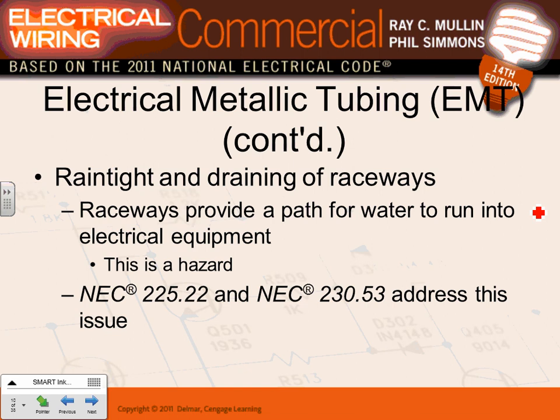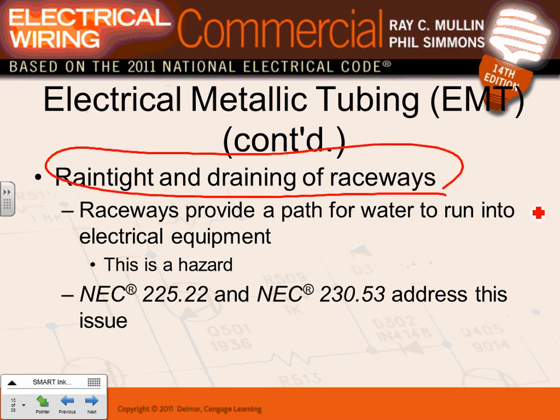Drainage of raceways: as you bring raceways inside the building, you don't want to channel water from outside to inside and dump it right above your switchgear. You have to provide a path for water to drain away from electrical equipment. As you bring conduit in, you need an elbow so that water can drain away. Inspectors and project managers will be looking for these drainage fittings as you bring conduits into the building.